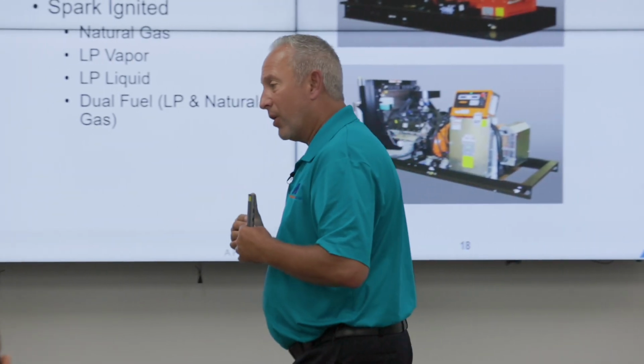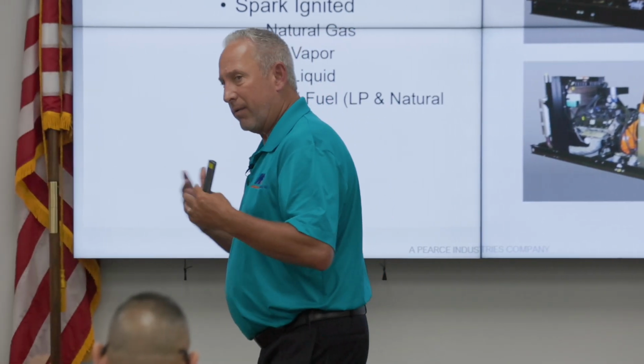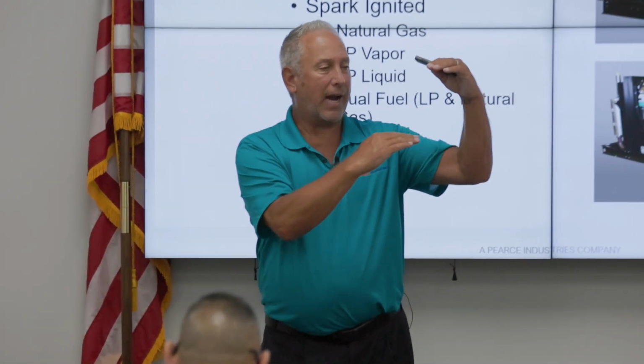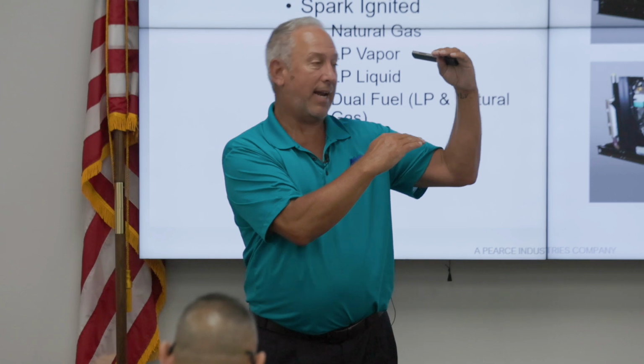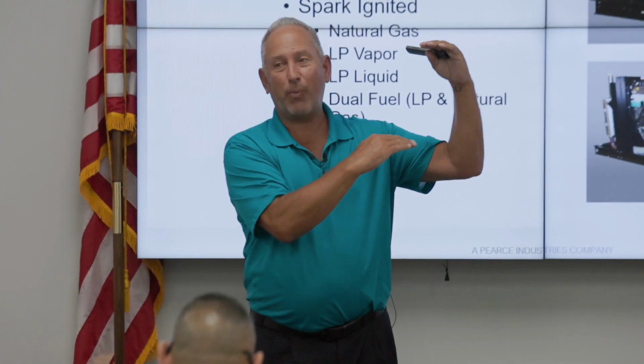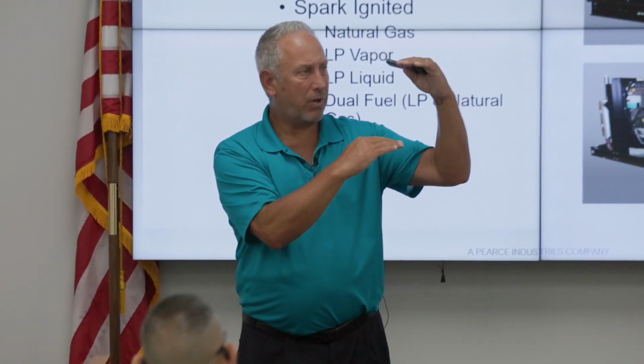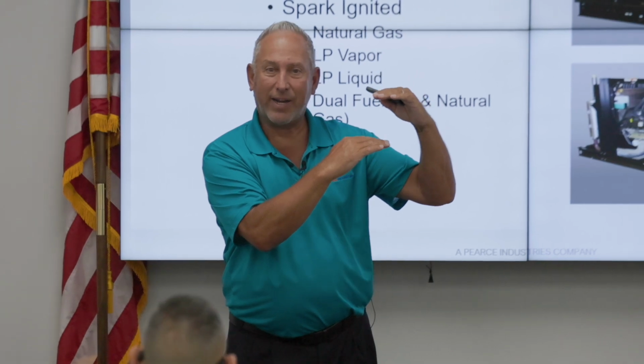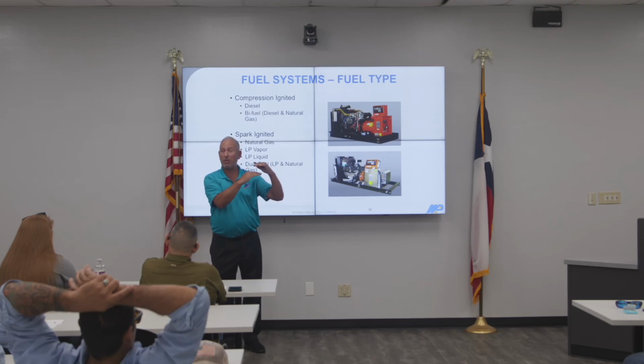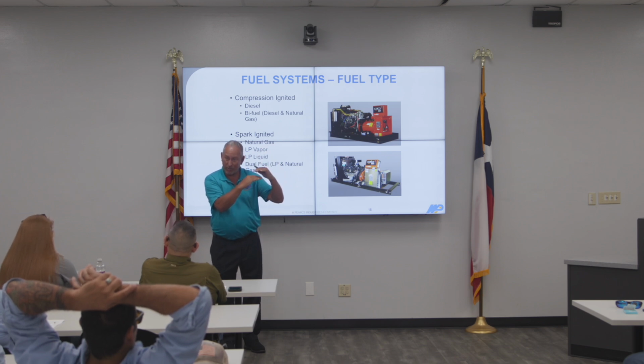So the governor doesn't know what's going on. The governor goes, okay, I need this much fuel to maintain 1800 RPM. Now we start bringing natural gas in. Now it goes, oh, I need less, I need less, I need less. Now I only need this much fuel to do 1800 RPM. So it starts to naturally back off using your diesel.